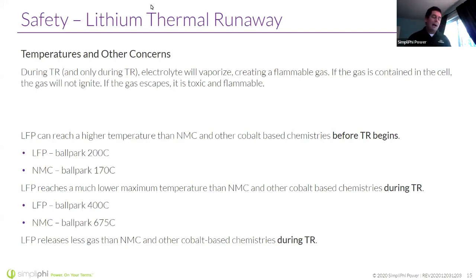So when we talk about LFP, or lithium iron phosphate, we can reach a higher temperature before thermal runaway begins, which is good. So if we're not starting thermal runaway until, say, 200 degrees Celsius, but a similar product with an NMC chemistry is reaching thermal runaway at 170 degrees Celsius, that lower temperature means that that product may face thermal runaway more often or under less extreme circumstances.